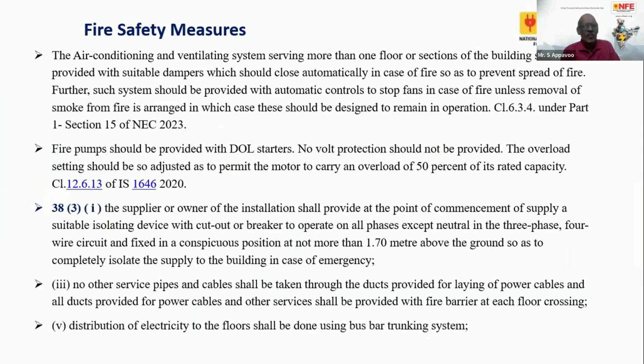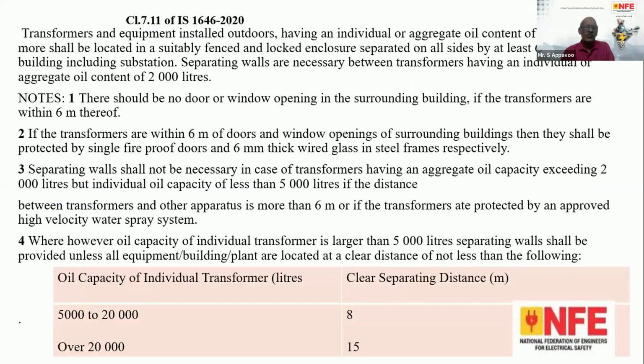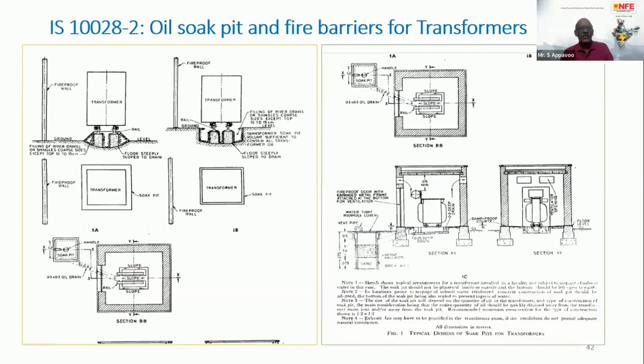So coming to the fire safety measures, IS 1646, beautiful, it was reaffirmed in 2015 and reaffirmed in 2020, and provides very good measures for protection of building premises. These are the provisions that have to be observed by the occupier. And the transformers also have to be erected depending upon the oil content. There should be a separation distance between the transformers and the building to avoid propagation of fire to the building or to minimize the damage during the fire. This is the standard available in IS 10028, how the soak pit has to be constructed, how the fire barrier wall has to be constructed for the outdoor installation as well as for the indoor installation.